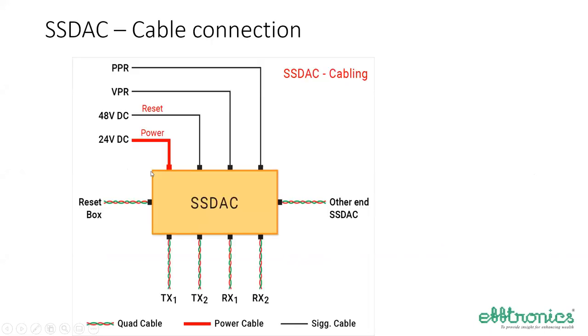So what type of cables and power supplies have to be used? It works on just one power supply, 24 volt DC from the IPS, that is sufficient. If this is the SSDAC of one end, it is connected to the two transmitters and two receivers by the communication cable. This cable comes along with the wheel detector coils. There is no need to provide them separately, and they can't be provided separately. And this is the one which exchanges the count with the other end SSDAC, it is a communication cable. And a power cable comes with 24 volt DC and a 48 volt DC reset voltage. It is received here from the reset box.